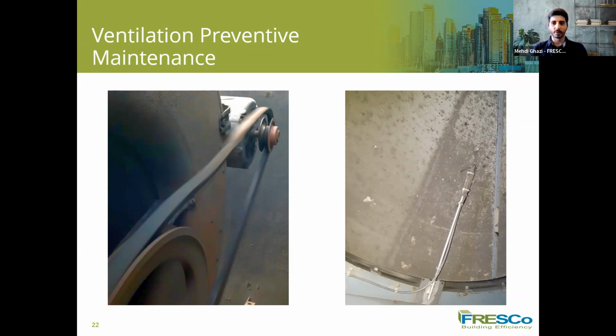Ventilation. We all know makeup air units on our roofs, and we at Fresco have walked hundreds of rooftops, and at least 50% of the makeup air units we are seeing are missing filters, or they have fully loaded filters, or the filters are mashed. So filters are one of the things that we need to check on our makeup air units. We need to make sure that the filters are getting replaced on time. Sometimes the size of the filters that we have been using is discontinued and not in the market anymore. So we need to make sure that we can adjust the filter frame with more metal sheet or something, so we can use the filter sizes that are in the market.